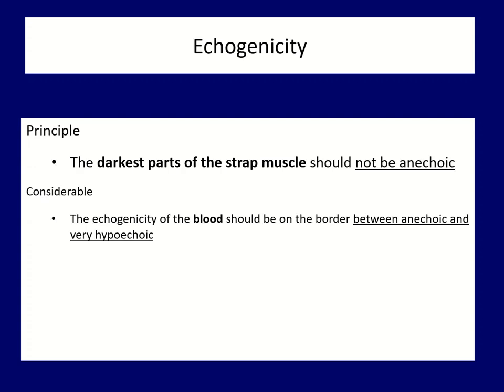The second task is the appropriate setting of the echogenicity. Essentially, it means that the darkest part of the strap muscle running ventral to the thyroid should not be anechoic, that is not without echoes.